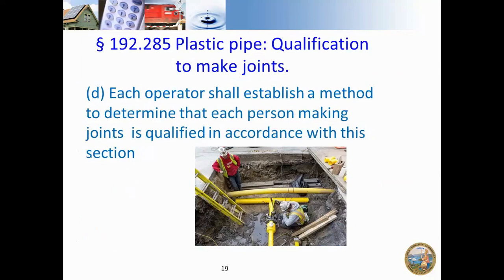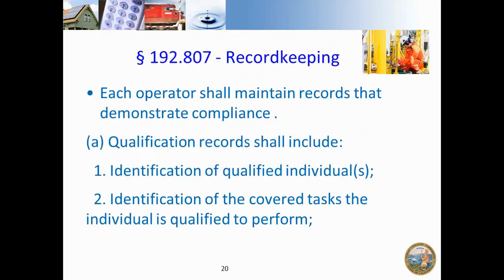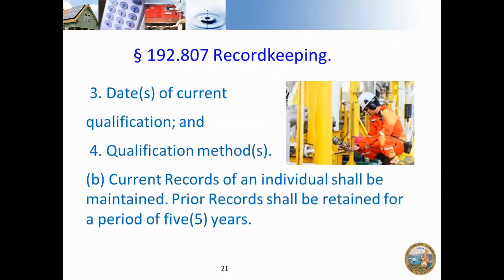Each operator shall establish a method to determine that each person making joints is qualified. Records should be kept — this qualification record should include: identification of the individual, covered tasks that the individual performed, date of current qualification, and the qualification methods used. Records should be kept for five years.